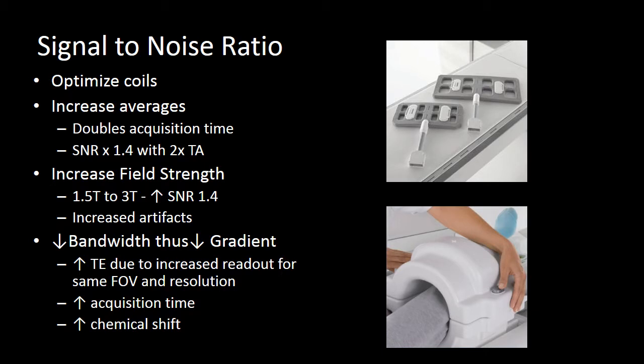So how do we improve signal-to-noise ratio? The best way is by optimizing which coil you're using and coil positioning, because the strength of your radio frequency signal drops off rapidly as you move away from your source. You can also increase your number of averages, which means acquiring each image twice to get twice the amount of data. Getting twice the data takes twice the time, and you only get an improvement by the square root of two — a signal-to-noise ratio increase of 1.4 takes twice the time.